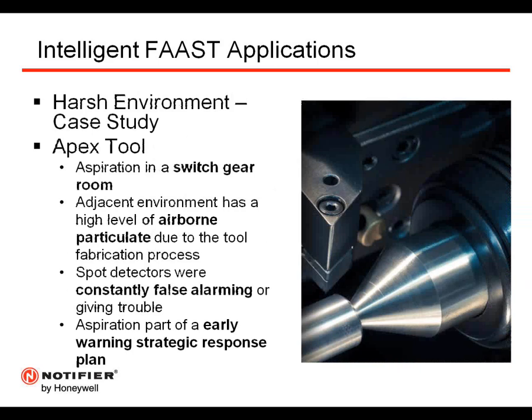Apex Tool, this is in North Carolina. They make hand tools like Craftsman hammers and saws and things like that. Their insurance required that they had early warning smoke detection in their switchgear rooms. As you can imagine, as a byproduct of working with all that metal, they have a very caustic environment, and there's also a lot of dust. So spot detectors that they previously had installed in the switchgear room were prone to nuisance alarms or dirty detector warnings. So they implemented FAAST because of its filtration methodology.